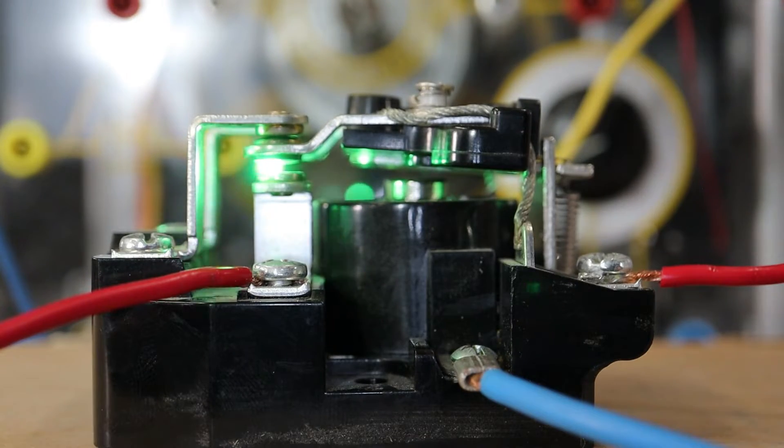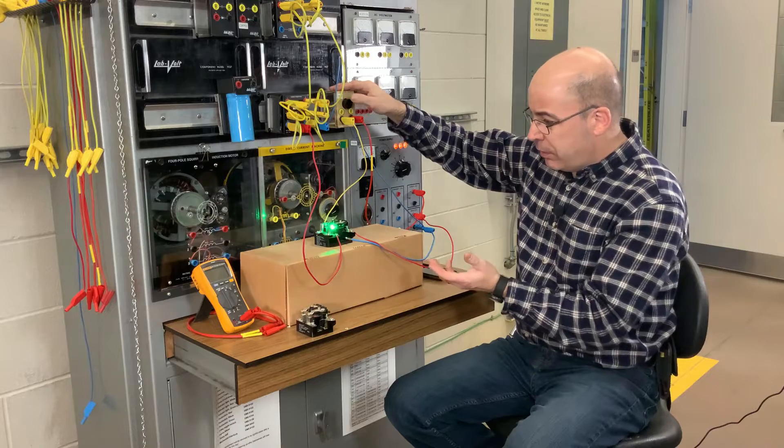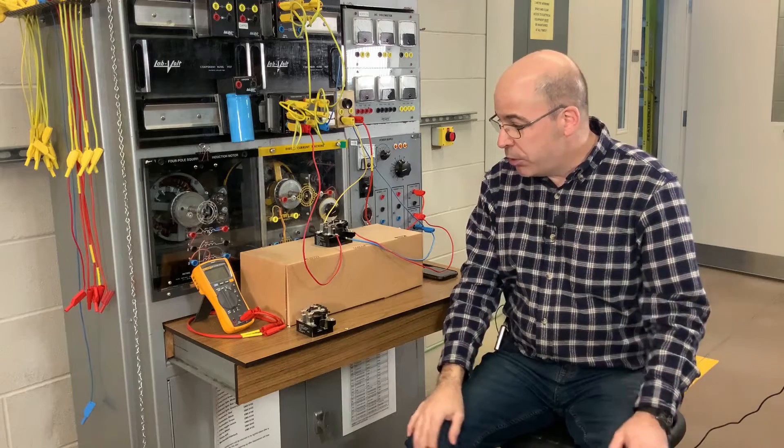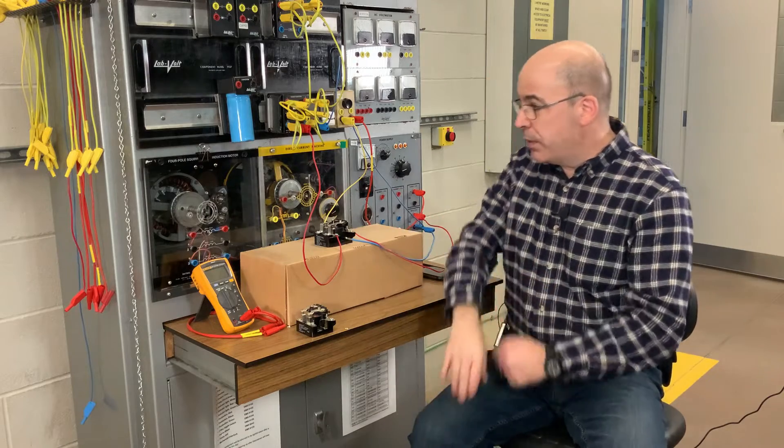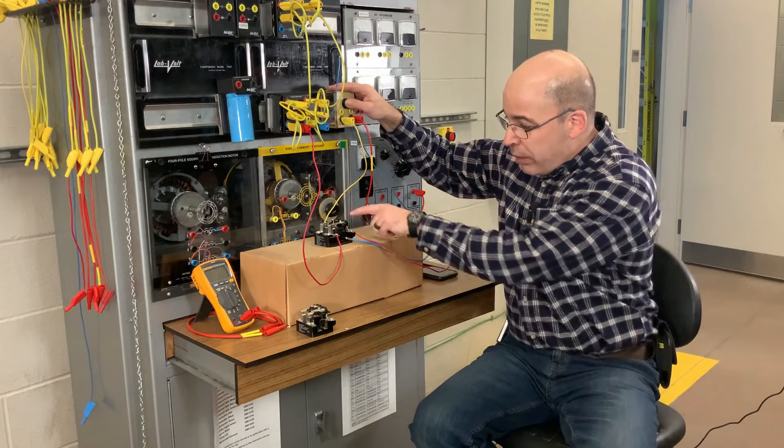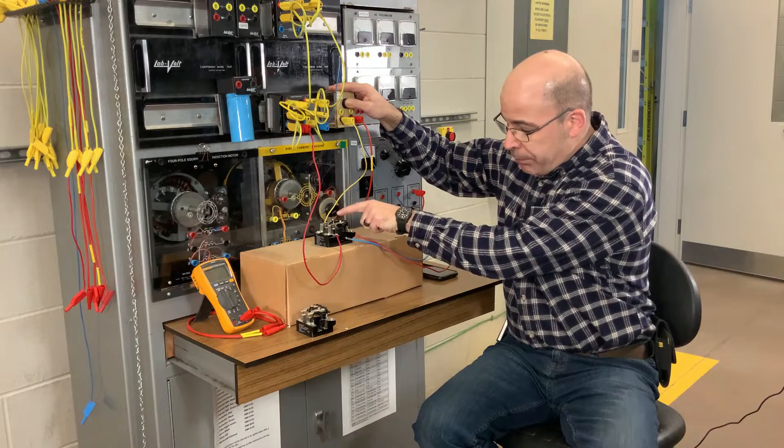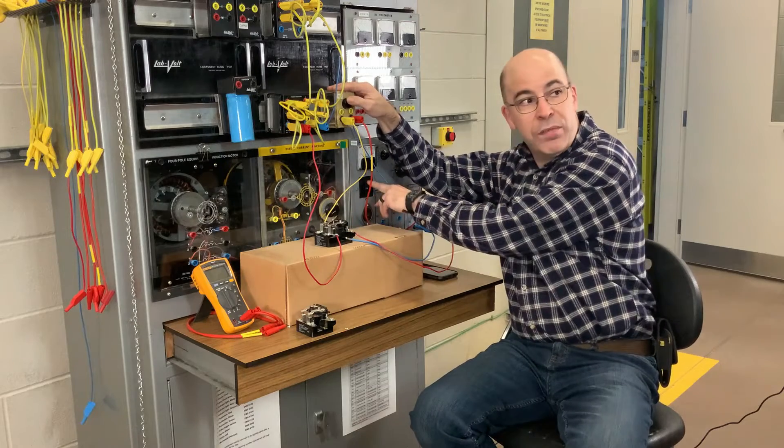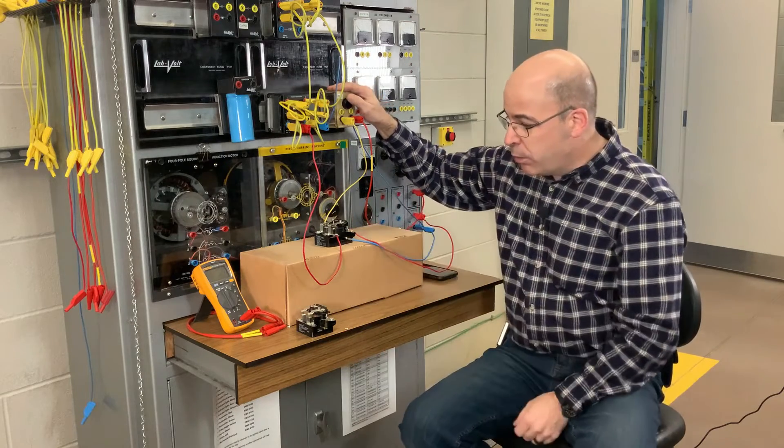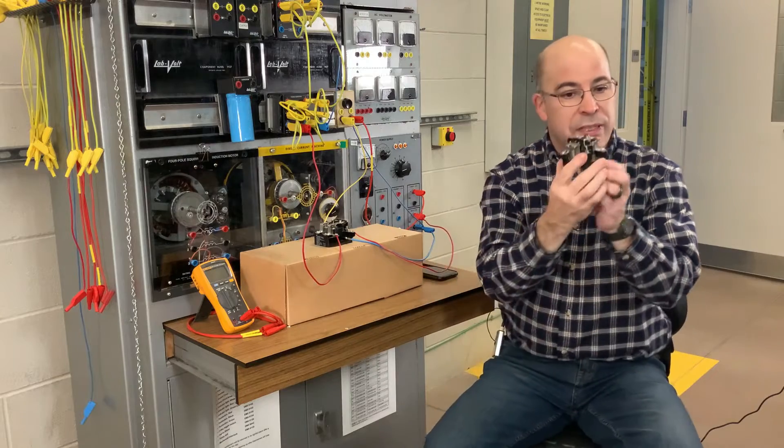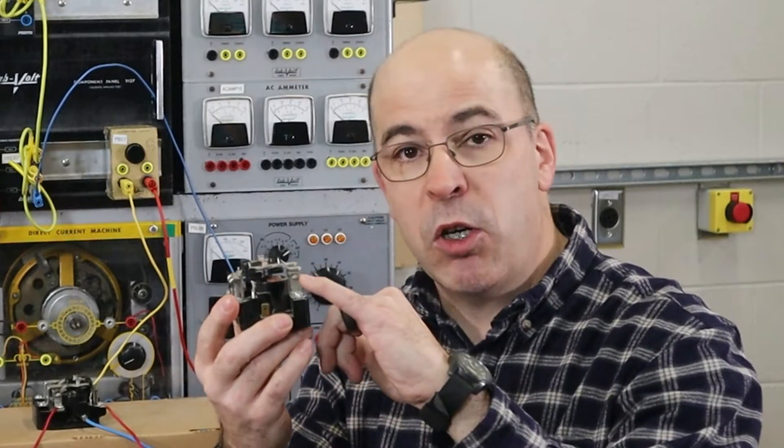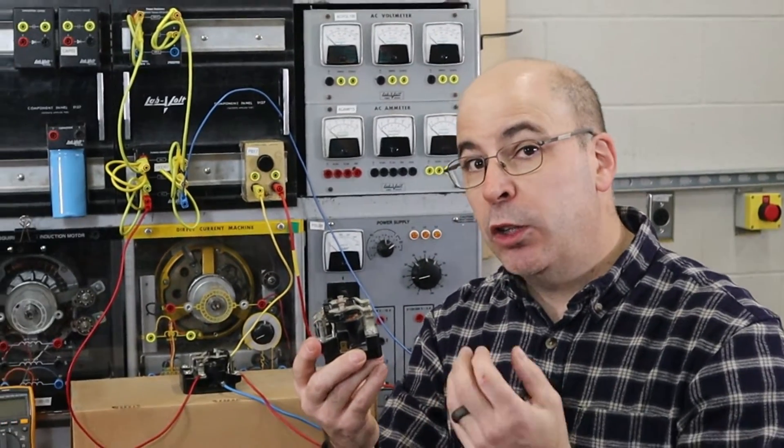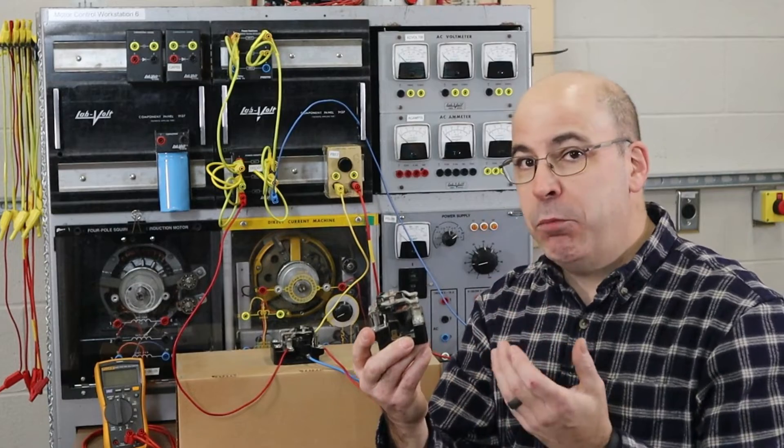Unfortunately, I can't do anything to turn this off. I was able to turn off the circuit by energizing the coil. I made the contacts or the armature close again, and then once this was in the closed state, I turned off the power. But what it goes to show is that the current is literally jumping or arcing across the air gap that exists, taking what we call a low impedance path. This is a problem.